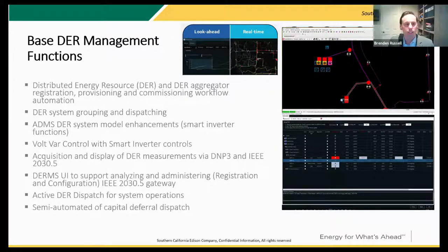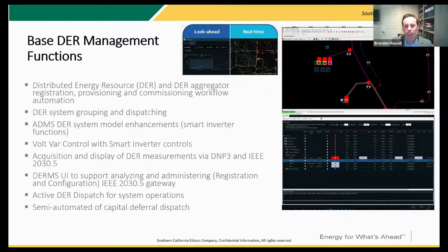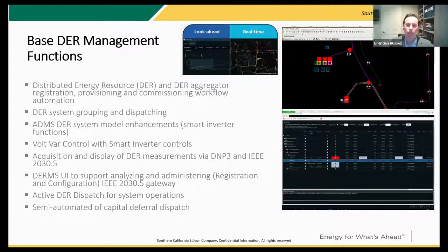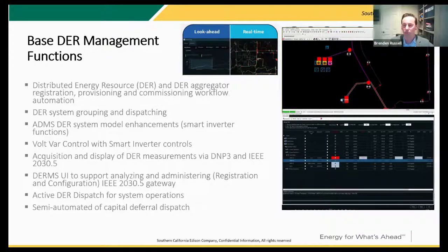Part of our Release 1 is also deploying our base DERMs functionality. We've been partnering with General Electric to develop this not as a standalone solution, but integrated into the ADMS. In California, we have a number of business drivers seeking this capability sooner rather than later. Part of the Rule 21 smart inverter working group work we're doing in California — we have a goal to enable IEEE 2030.5 communications, which is going to be the de facto communication protocol for DERs and utility-to-DER communications. So we're building out the 2030.5 communication headends and the infrastructure tied back into the ADMS to bring in that data and start streaming it into our operational systems.